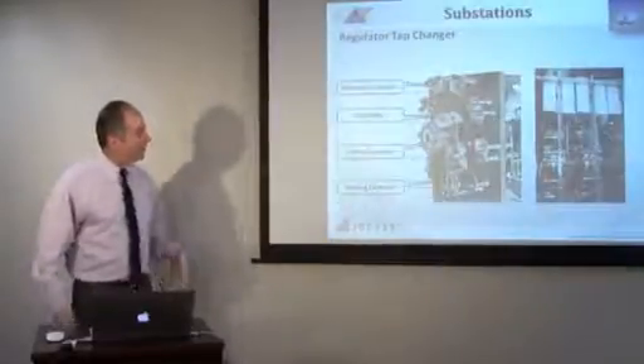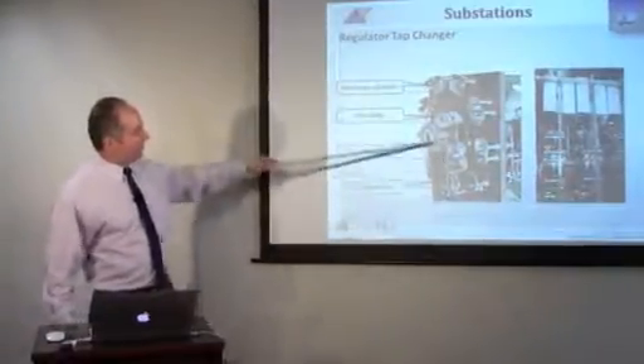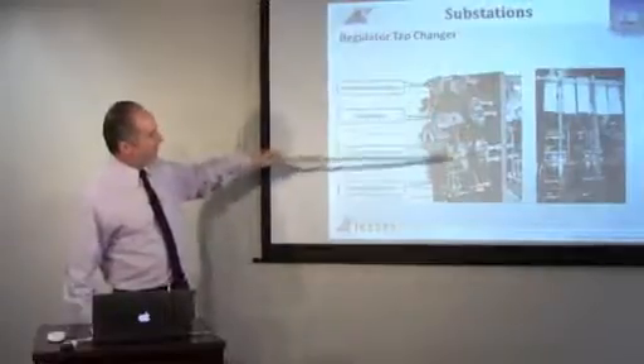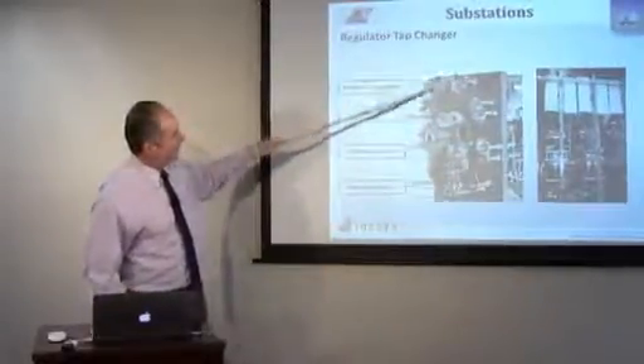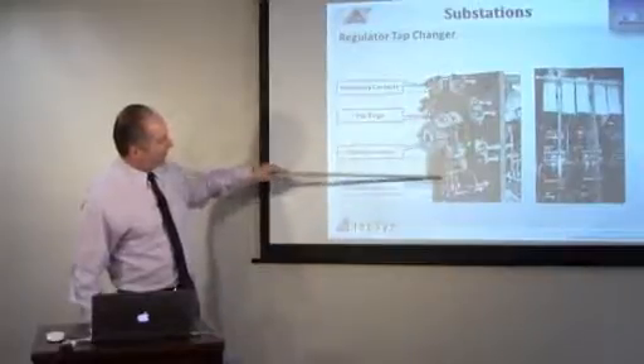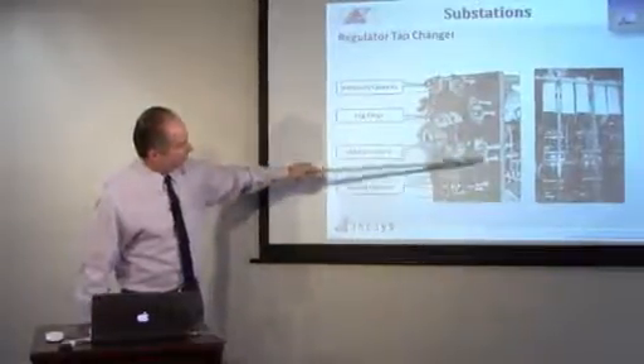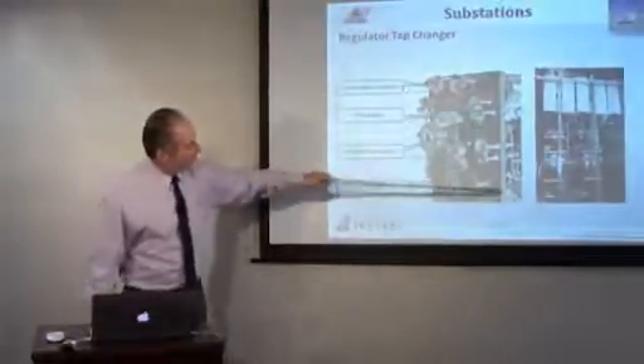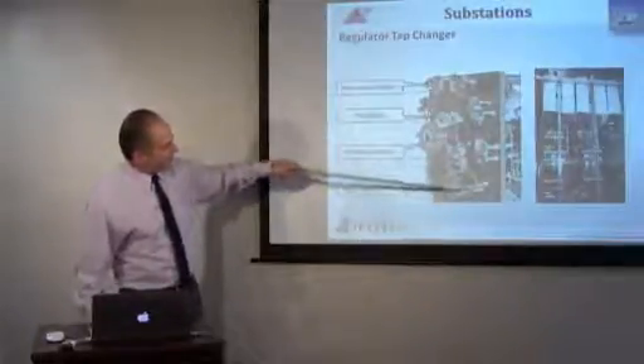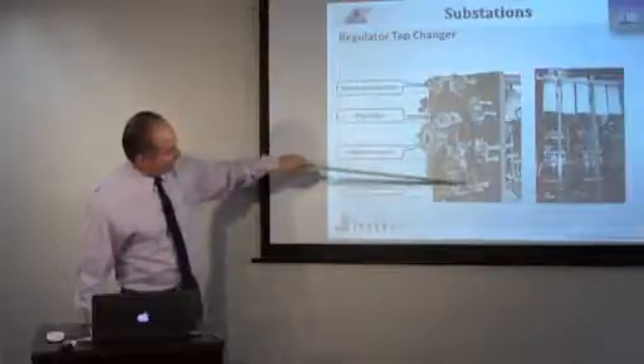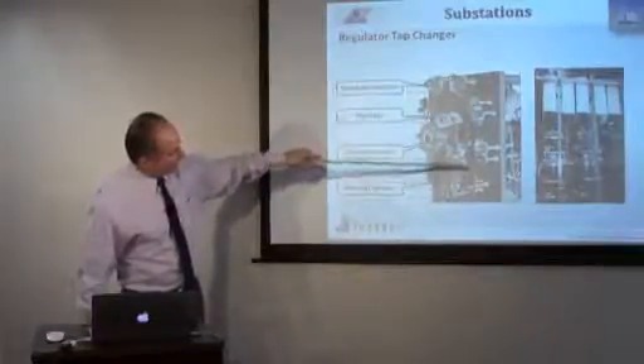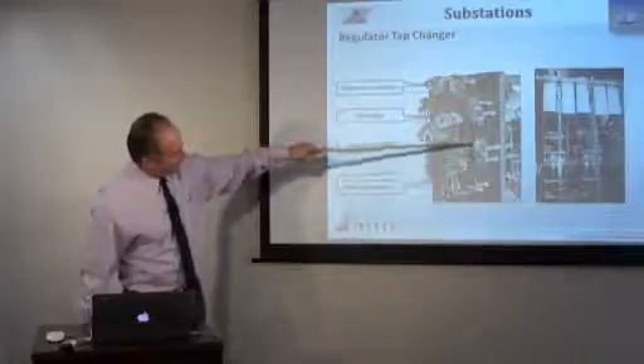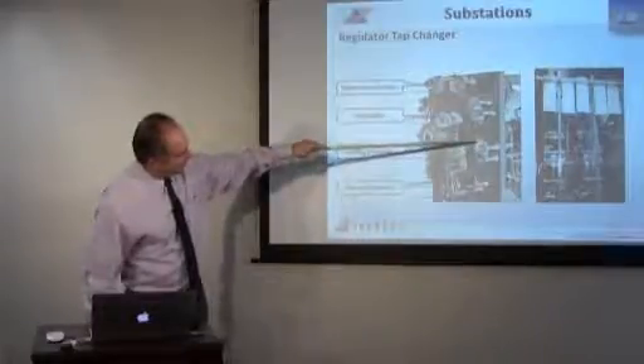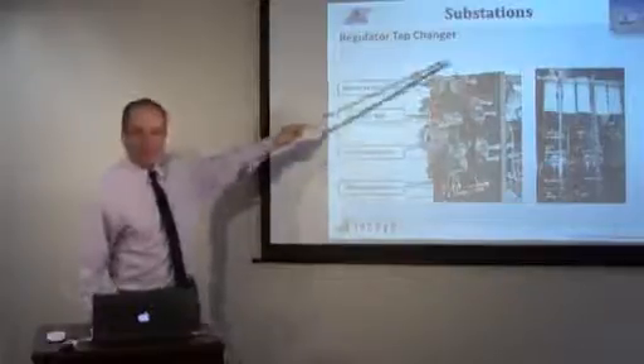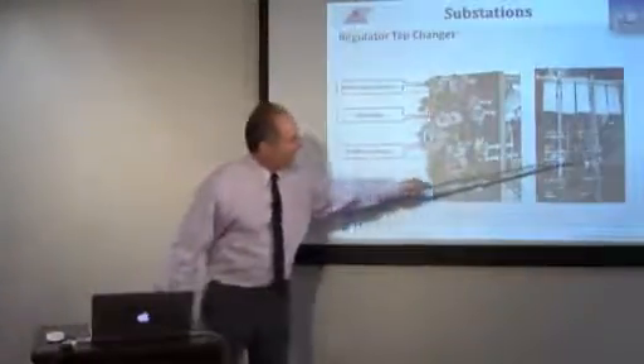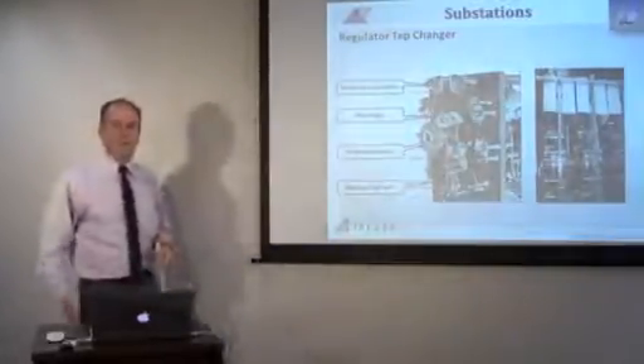Roughly how that works. So in the 3-phase regulator, you have this shaft that's turning, and here's your tap positions onto the windings all the way around. And as this goes around, these are fixed taps going to each of the windings, and then you're going to make between both these connectors on this piece, and then if it's moved, one connector's here, one connector's here, and then if it moves again, both connectors are here, and then one connector here, and then here. You can see how it kind of goes around. And there's all 3 of them lined up inside a regulator, just to give you an idea.